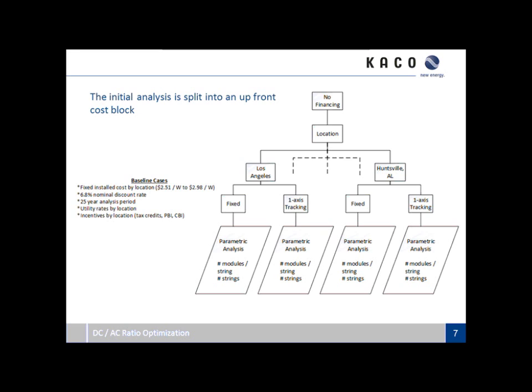To look at the initial analysis and simplify the interaction of all these variables, I blocked it into two cases. The first is a no-financing case, split into different locations, and within those locations, fixed and single-axis tracker racking types. I used SAM's parametric analysis tool to model a changing DC to AC ratio based on number of modules per string and number of strings. The baseline price per watt varied from about $2.50 to $3 a watt based on labor, land costs, and racking type. I used a discount rate of 6.8%, an analysis period of 25 years, and utility rates and incentives varied by location.